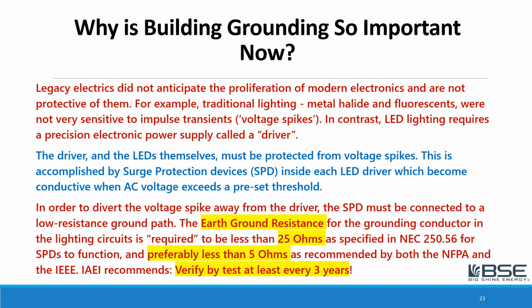In addition, for them to work, they have to be connected to a low resistance ground path because the surge protection device built into your equipment has to send that little voltage spike somewhere. And the place it wants to send it is to the ground underneath your building. It can't do that if the resistance is high. Now, the NFPA and the IEEE both recommend that this should be less than 5 ohms. There's a sort of implied requirement in the National Electrical Code to be less than 25 ohms. But even there was a loophole, and I'm going to explain about that in a minute.